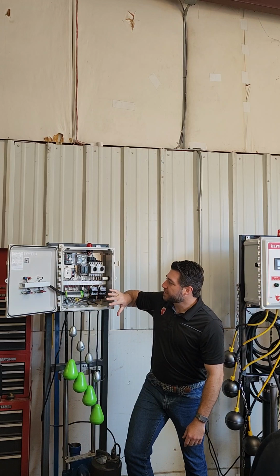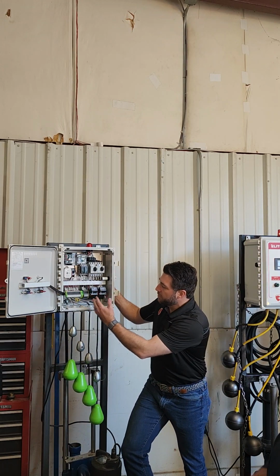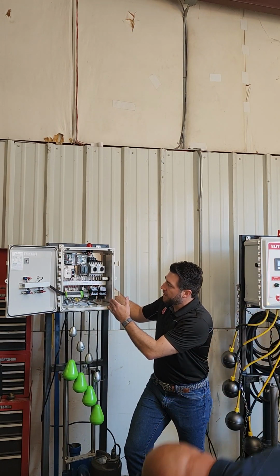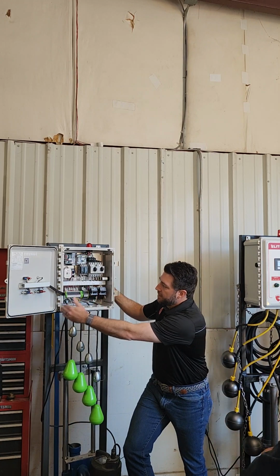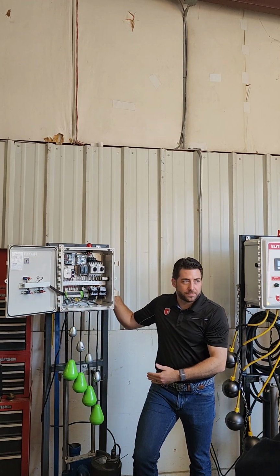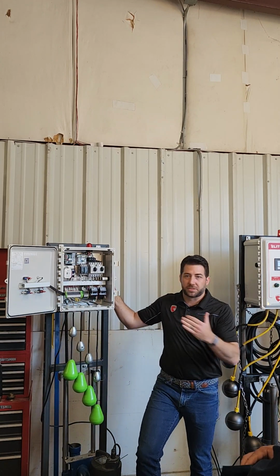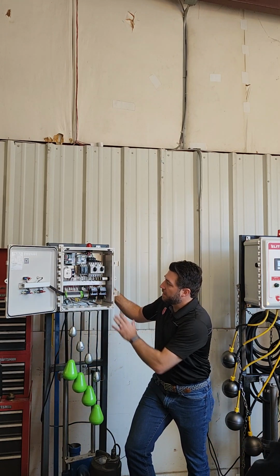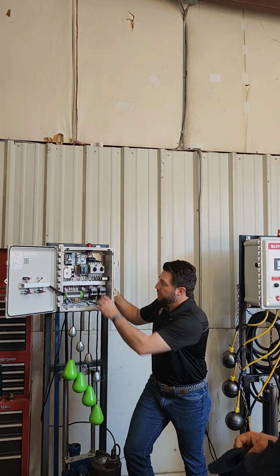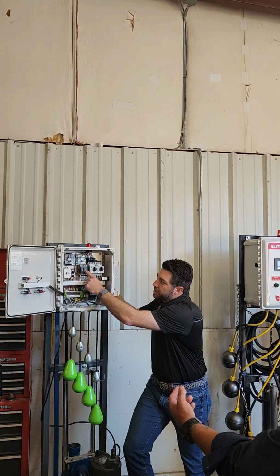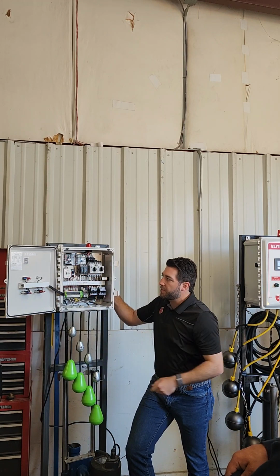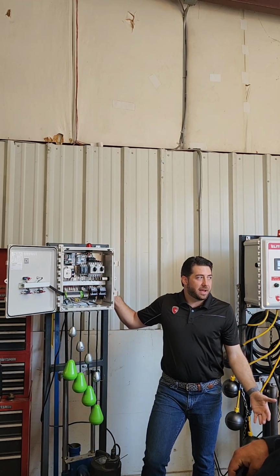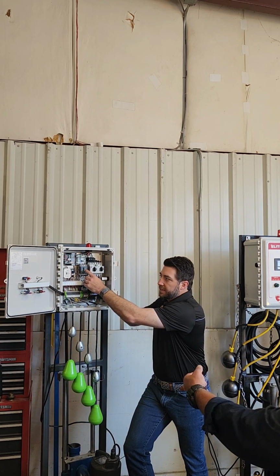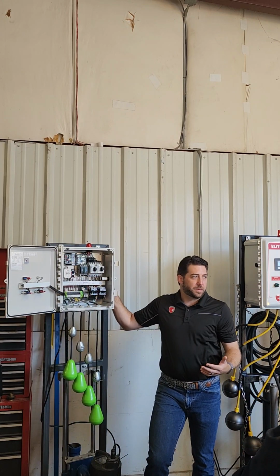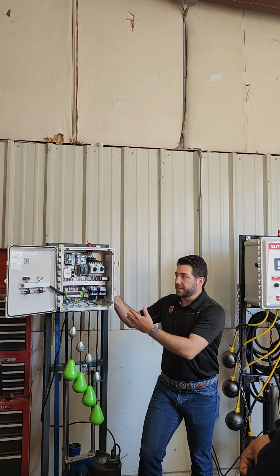But in this panel, we organize them with the high voltage on one side, the 3-phase on this side, and the low voltage, the control, on the other side. So this is going to be the same way. You'll see that kind of separation of the power in the panel. We do have a main disconnect switch here inside the panel for the incoming power. A lot of other panels may or may not have that. So if you don't have a main disconnect inside the panel, you're going to need to know where to be able to shut off the power before it gets into this panel.